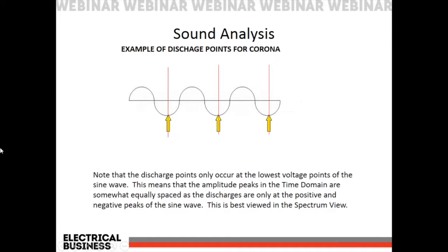So going forward, the reason why we diagnose this as corona has to do with where the discharges happen in the sine wave. The discharges here are happening on the negative peak of the sine wave. Those negative peaks are where ionization occurs the most, which gives us our even spacing. If you look at where the arrows are pointing and where the discharges are happening on the sine wave, that's the reason why our corona time series has evenly spaced discharges or events, because of where the ionization is occurring. And that allows us to diagnose that this is corona.